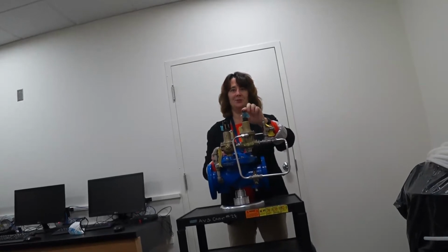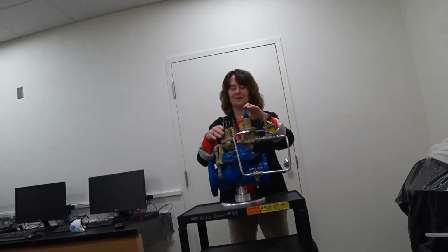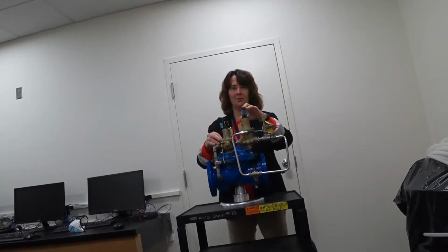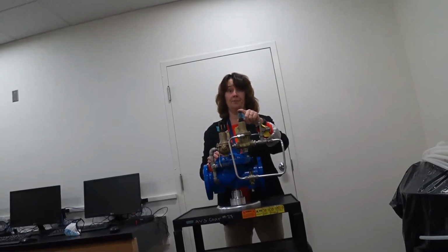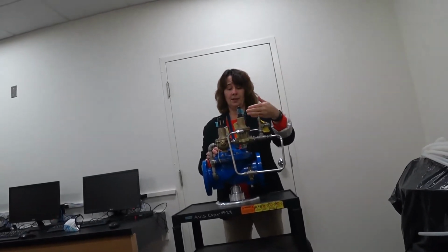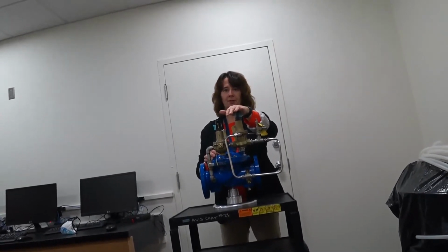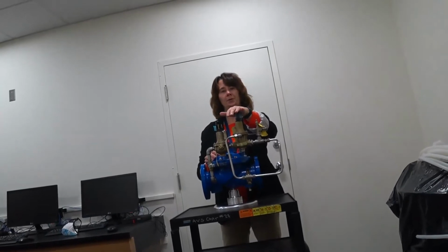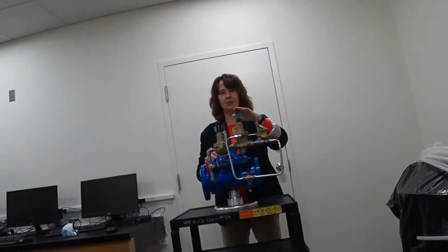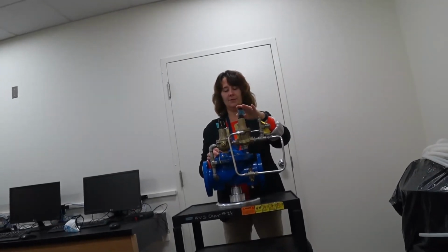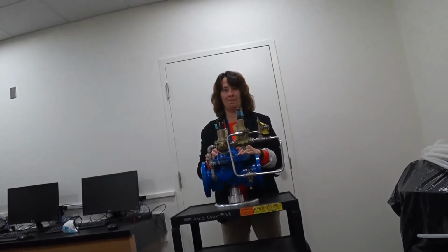If this one is closed and controlling it, this one could be doing lots of different things, and it's basically like a person in the background yammering at you. It doesn't matter what it wants. This one's the dominant valve, okay? So when you're looking at piloting, the valve that's in the front, or the upstream valve, always has priority over control of the main valve, okay? So the conditions for operation of this pilot valve will control this valve first, okay?